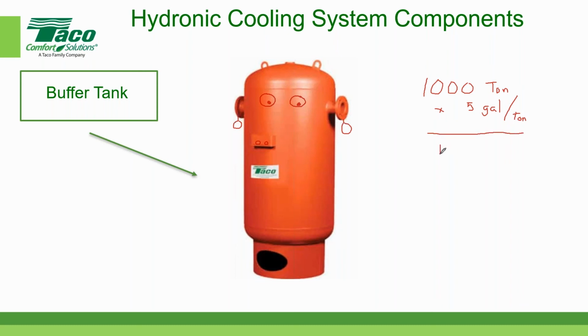But the tank doesn't have to be 5,000 gallons because some of that volume is also in the piping system. So we subtract out the volume of water in the piping system. And let's assume we're just going to make up a number for tonight's discussion. Let's say that the piping system had a volume of 4,000 gallons. So you'd subtract out the piping system, and lo and behold, your buffer tank would be 1,000 gallons. So it's as simple as that. You have to go back to the chiller manufacturer and they tell you what the gallons per ton needs to be. The general industry average is around 5, but some manufacturers want slightly more, some a little bit less. So there you go.